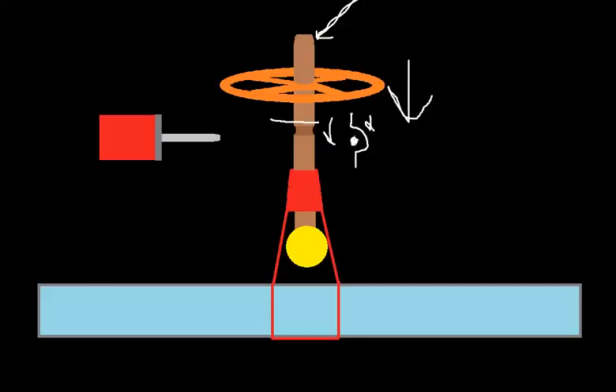But as this starts to go down, it actually pushes that arm out, and it changes the state of this valve. So you'd have your fire alarm hooked up to the contacts that are internal on here, or come in normally closed if you wanted to cause a trouble. And we'll talk about that in a little bit. And so that would change the state. So you start to turn this, it's going to cause a condition on your fire alarm panel.